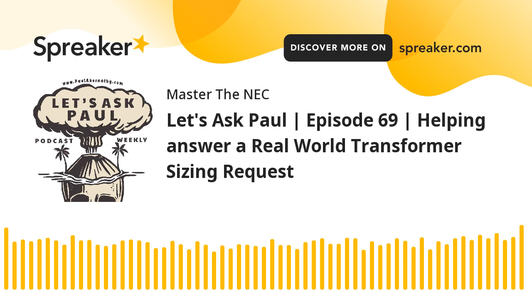Now, when it comes to the building, the restaurant, there is a possibility, since you have this voltage class there, let's say it was to the building as a service, you have the 480 coming to the building, say 480, 277, then you might be able to get another service to the building that ultimately may be cheaper than buying a transformer and doing all the associated wiring, all for just one piece of equipment. Again, it may be something that you could put in another panel, another service drop, and the utility will bring it over. It's only supplying one load, but if they get this one piece of equipment, it might expand their horizon to other pieces of equipment.